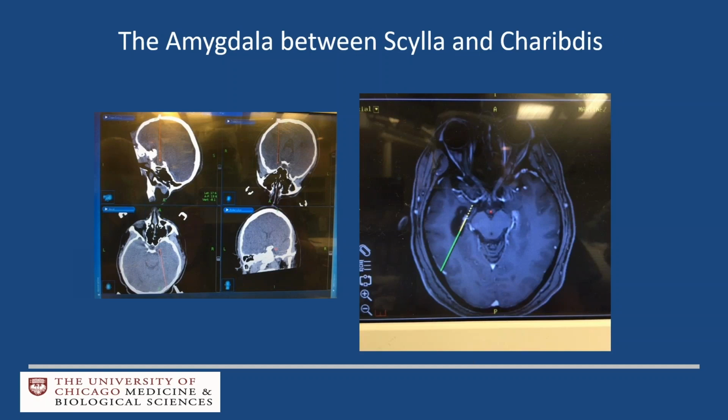The other most common application for epilepsy is that we do amygdalohippocampectomies now almost exclusively as interstitial laser ablations, and there you have to be sure that you cover the medial parts, but you don't start to burn the tentorium, to avoid cranial nerve deficits. For that purpose, you need to show on your scan that your fiber is exactly where you want it to be.